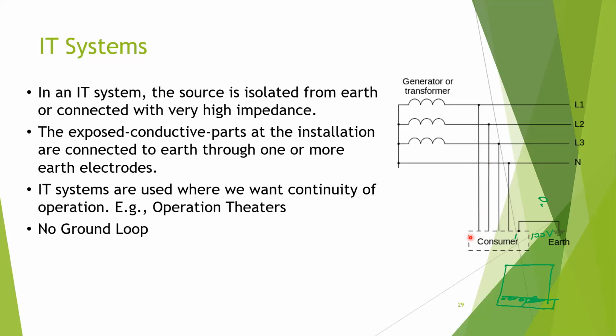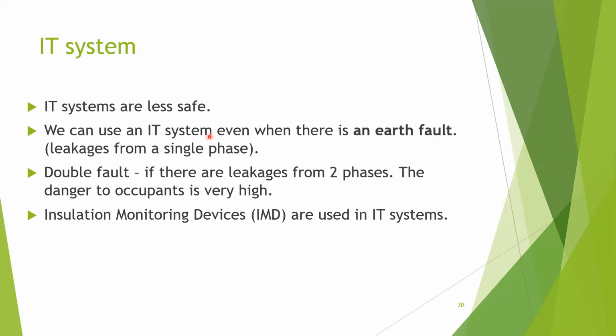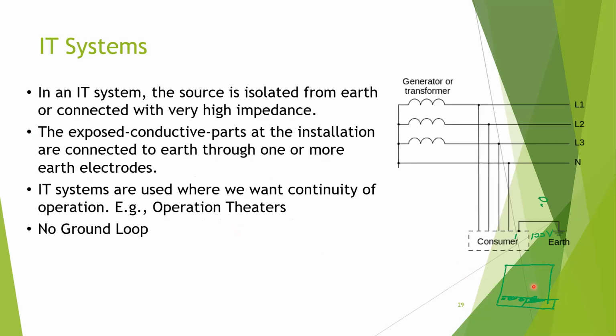So the main thing is, IT systems can be used with one earth fault. If you have two earth faults from two phases, you can't use the IT system. In IT systems, there are no RCDs and all. What we do have is an insulation monitoring device. I said that you have conductive floors in here. The conductive floors are isolated from the ground. So we have those things, and the enclosures are usually not made out of metal.